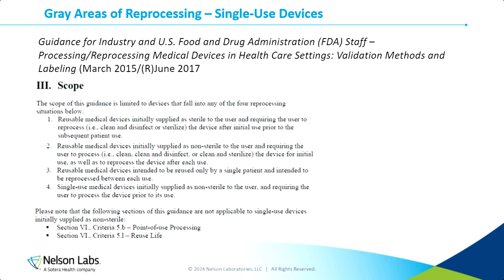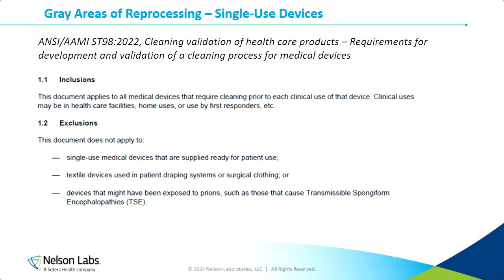So the first gray area that I want to go over is single-use devices. And what I mean by single-use devices are not devices that are supplied ready to use. I am referring to single-use devices that are supplied as non-sterile to the user and require the user to process them prior to use. So it requires the user to perform cleaning and disinfection or sterilization on these devices prior to use. And I want to bring this up because these devices are within scope of the FDA guidance document that was published in March of 2015. Additionally, these devices are in scope of AAMI ST98.